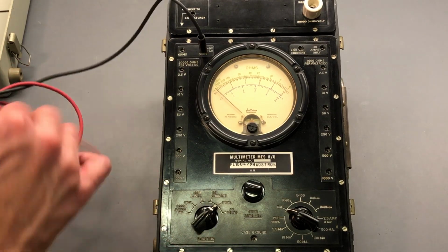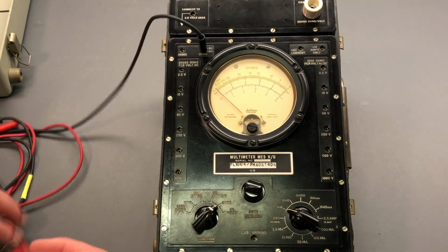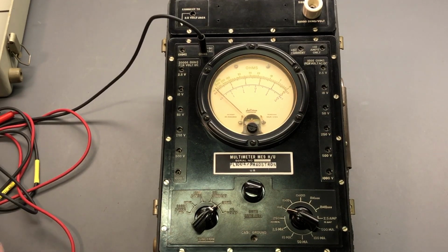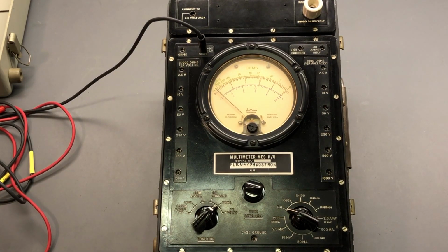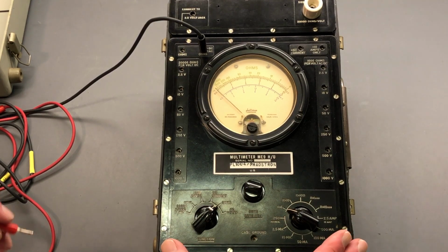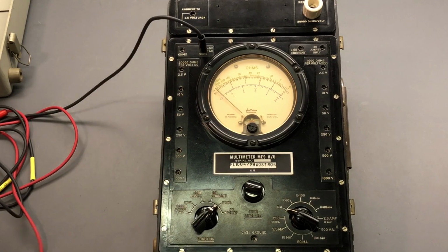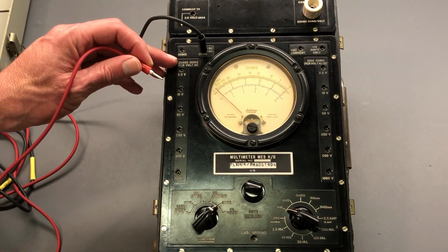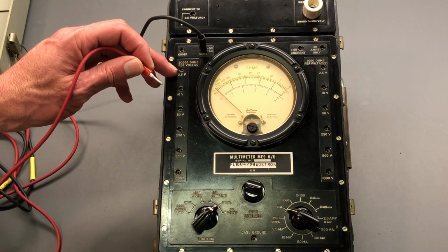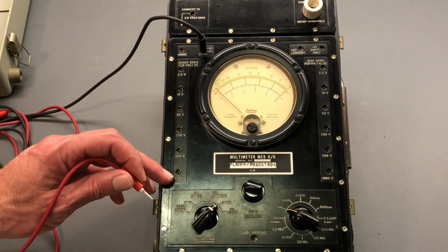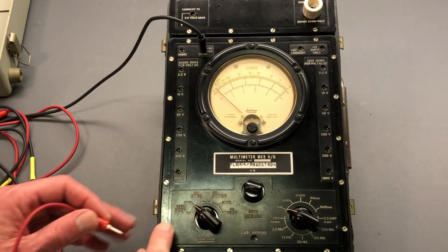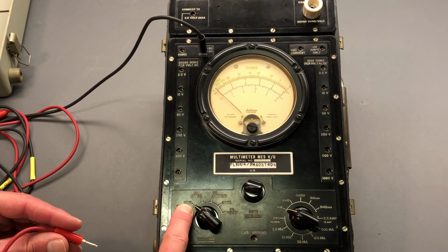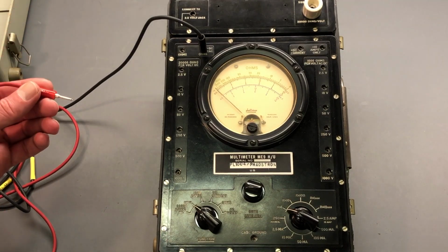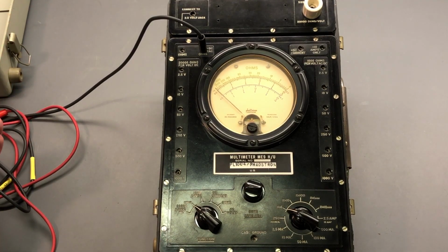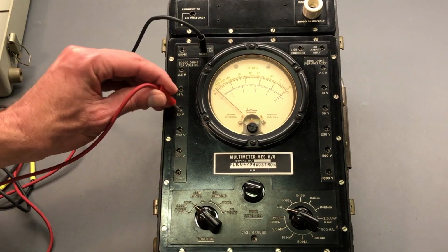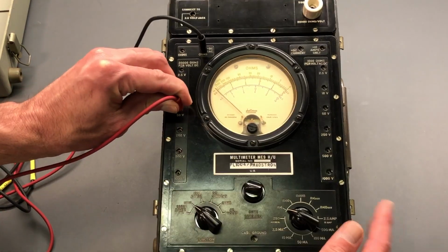Okay. Now, the positive test lead moves around quite a bit on this particular meter because the voltage ranges and some of the functions that this meter can do depend on where this lead is plugged in. So if you look down the side over here, it says 20,000 ohms per volt, and then it says 2.5, 10, 50, 250, 500, and 1,000. So if this is brought over here to 20,000 ohms per volt, normally you put this on direct reading, and let's say you were expecting to read something, perhaps 25 volts, 40 volts, something under 50 volts, you would plug this in like so.